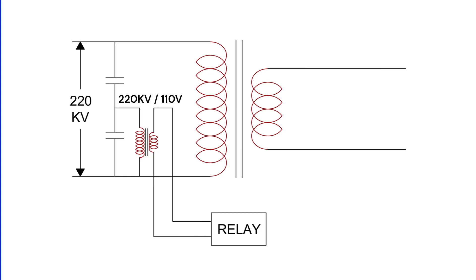For example, let's say a transformer's primary is connected to a 220 kV supply at 50 hertz. The PT ratio is 220 kV by 110 volts. So, the V/F ratio is 110 by 50, which is 2.2. At this ratio, the transformer operates safely. But what happens if the V/F ratio exceeds this value? That's where overfluxing occurs.